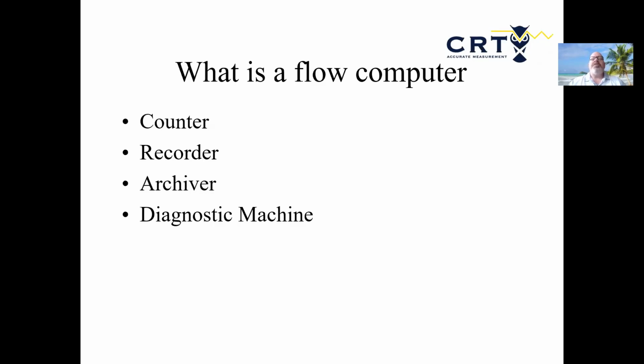With smart devices, Coriolis meters, we're polling for a lot of diagnostic information and bringing that back in. When you think about a flow computer as it sits on a measurement skid or a liquid skid, it has most of the measurement devices directly attached to it. So you're able to perform diagnostics to see how the instrumentation on the whole skid is working, because most everything comes back into the flow computer on these skids. So, powerful diagnostics tools that are built into a lot of flow computers out there.